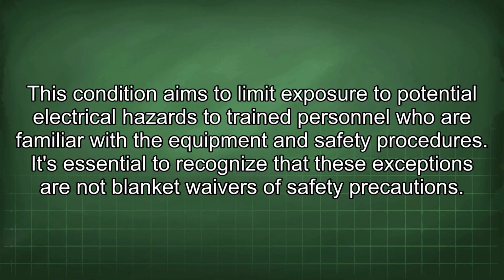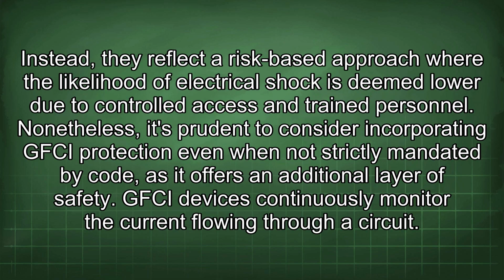safety procedures. It's essential to recognize that these exceptions are not blanket waivers of safety precautions. Instead, they reflect a risk-based approach where the likelihood of electrical shock is deemed low due to controlled access and trained personnel. Nonetheless, it's prudent to consider incorporating GFCI protection even when not strictly mandated by code, as it offers an additional layer of safety.